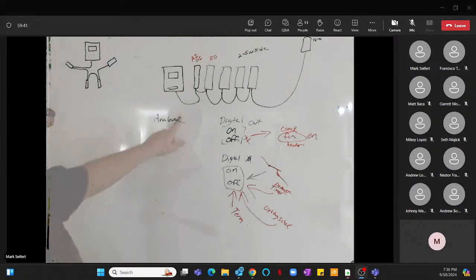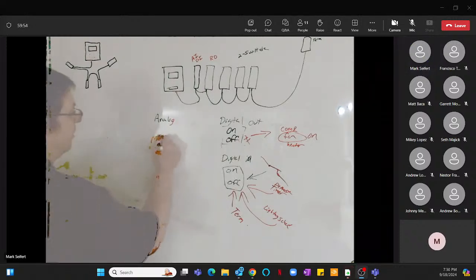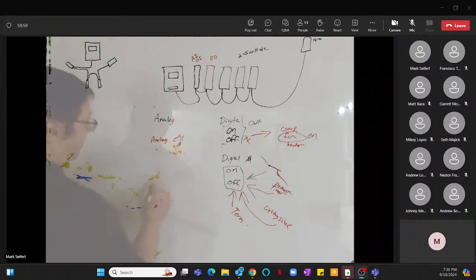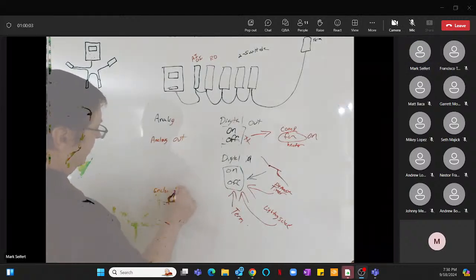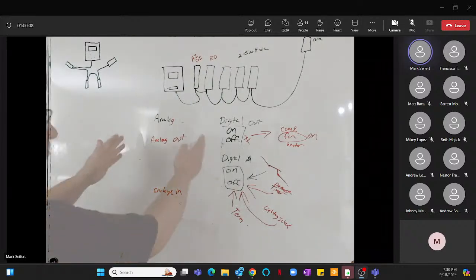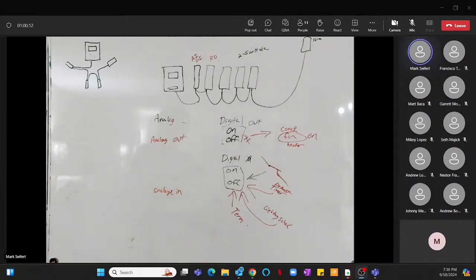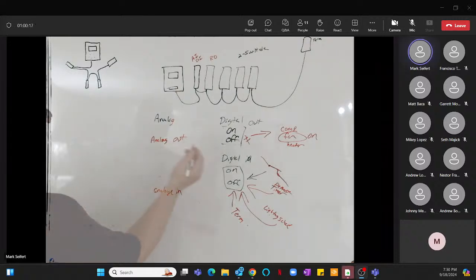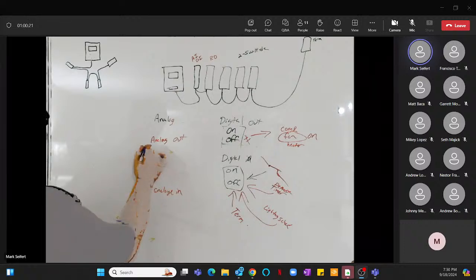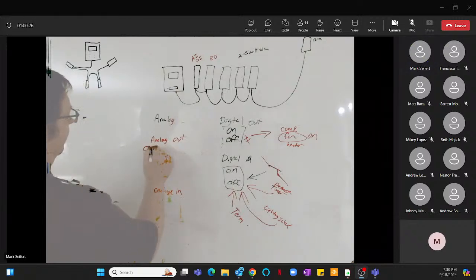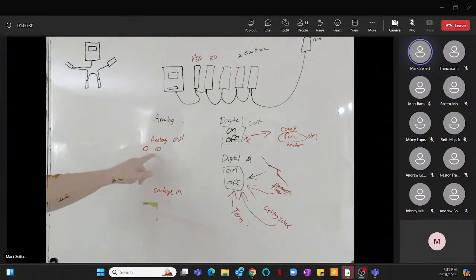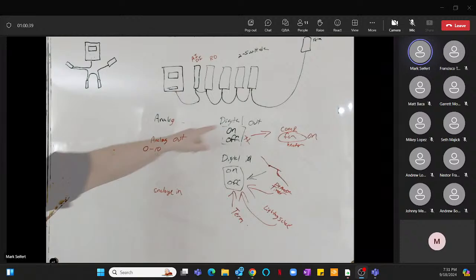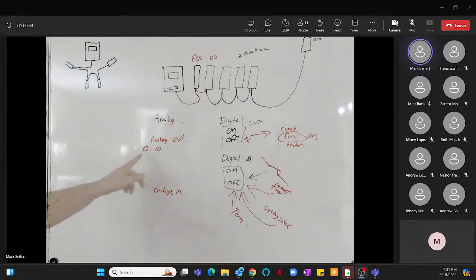Analog out, analog in. Same thing, only this has a spread that could go to infinity, basically, anywhere in between. You can set it up however you want. Analog out, most of the time we use 0 to 10 volts. We'll just call this a condenser. 0 to 10, and anywhere in between, including decimal points, but we'll forget that for now. So anywhere from 0, 1, 2, 3, 4, 5, all the way to 10. It's like an output, but it can get there. It doesn't go open and close. It's actually a number.